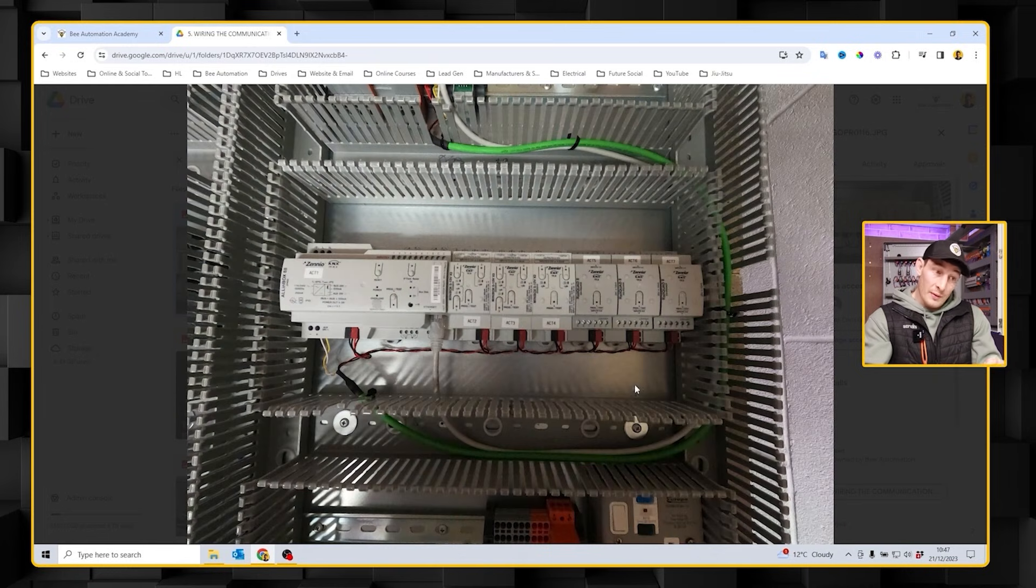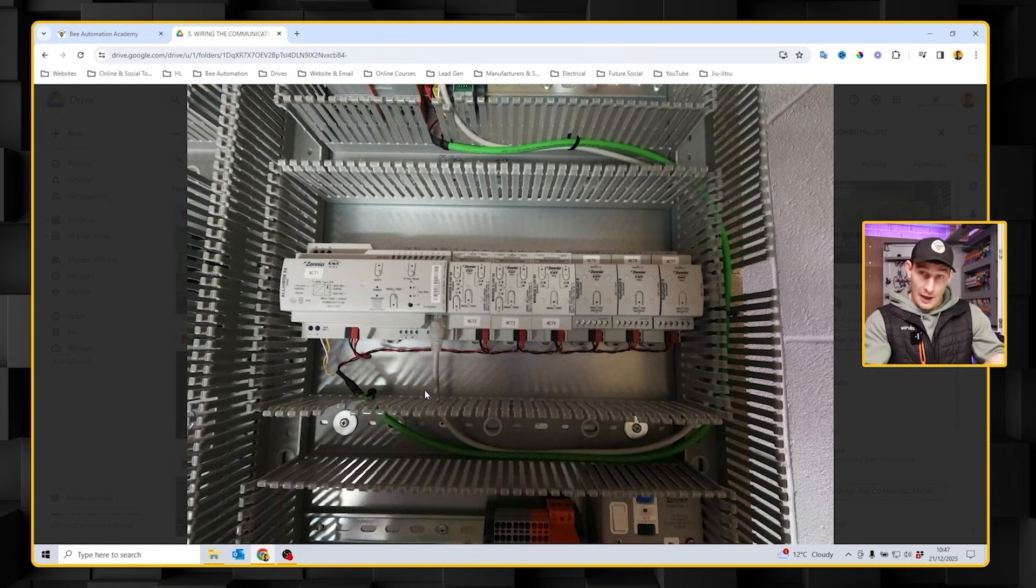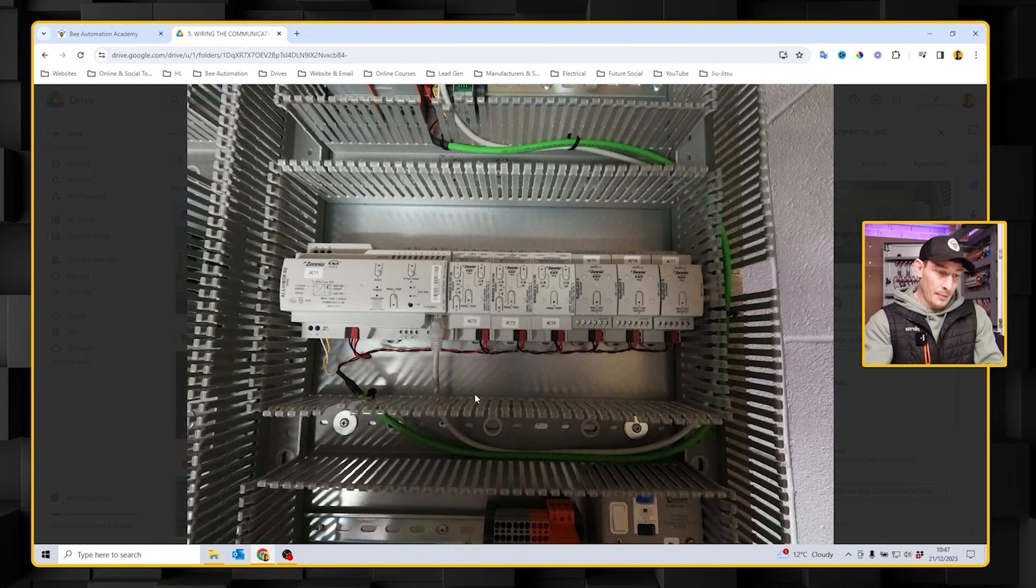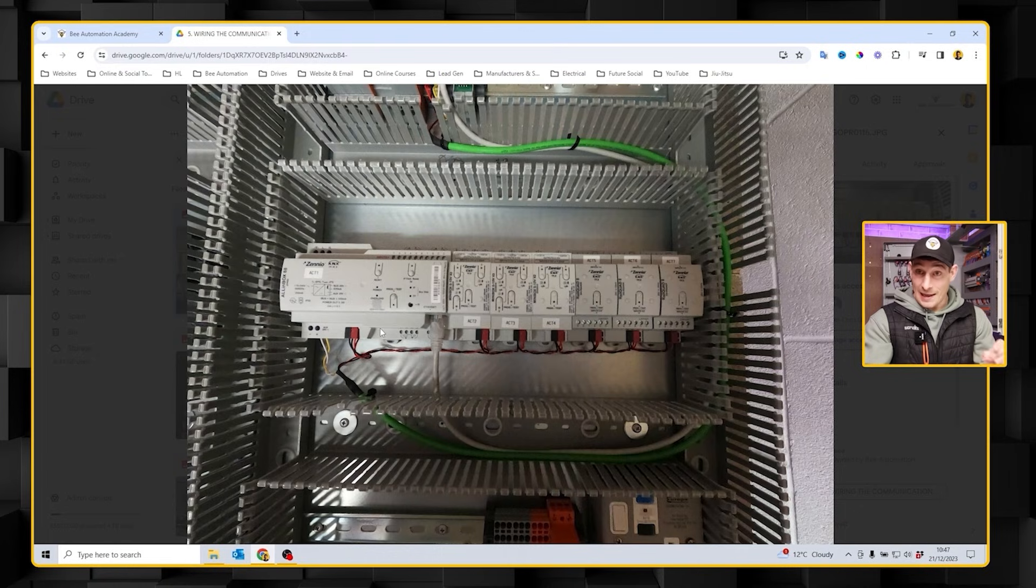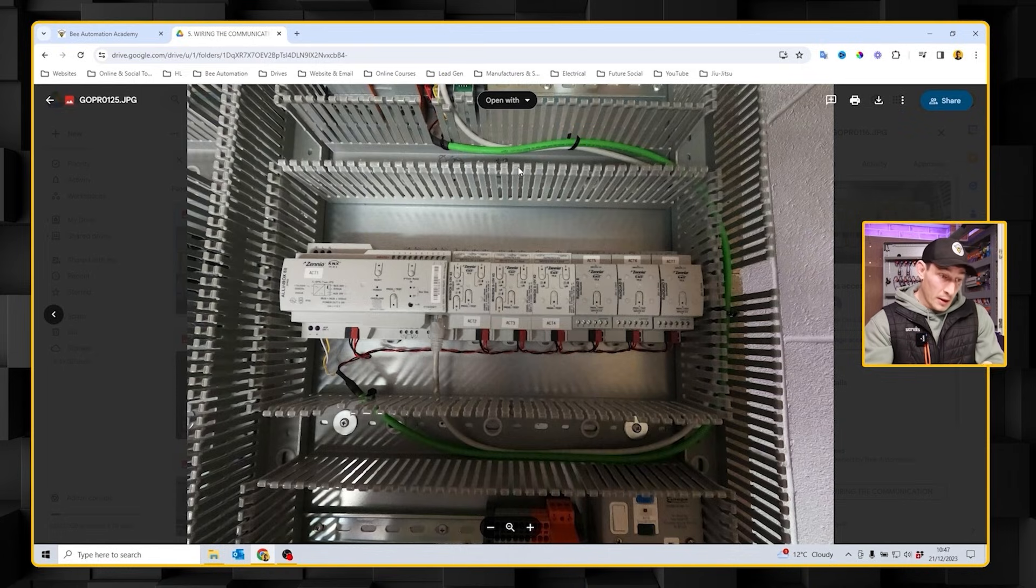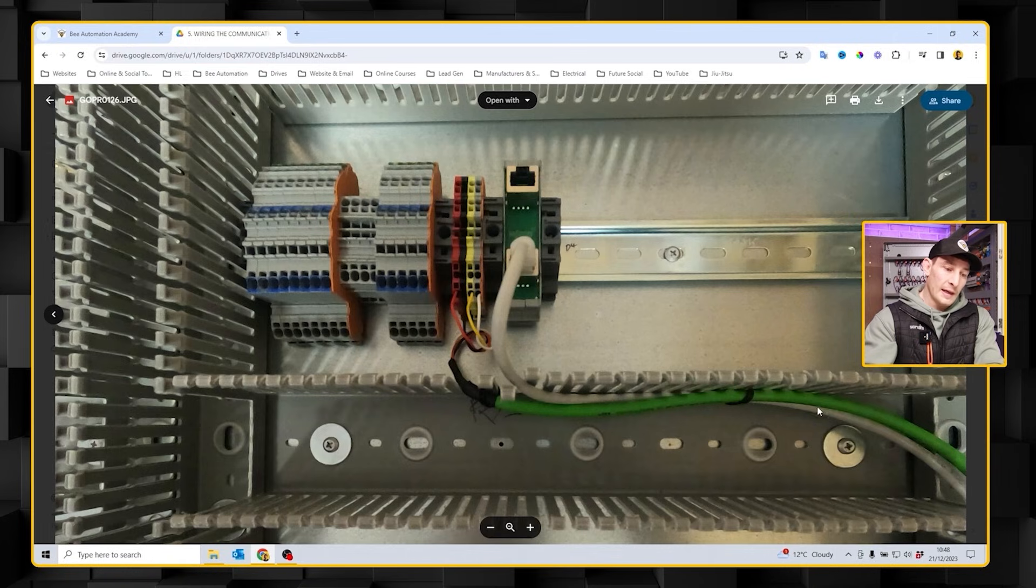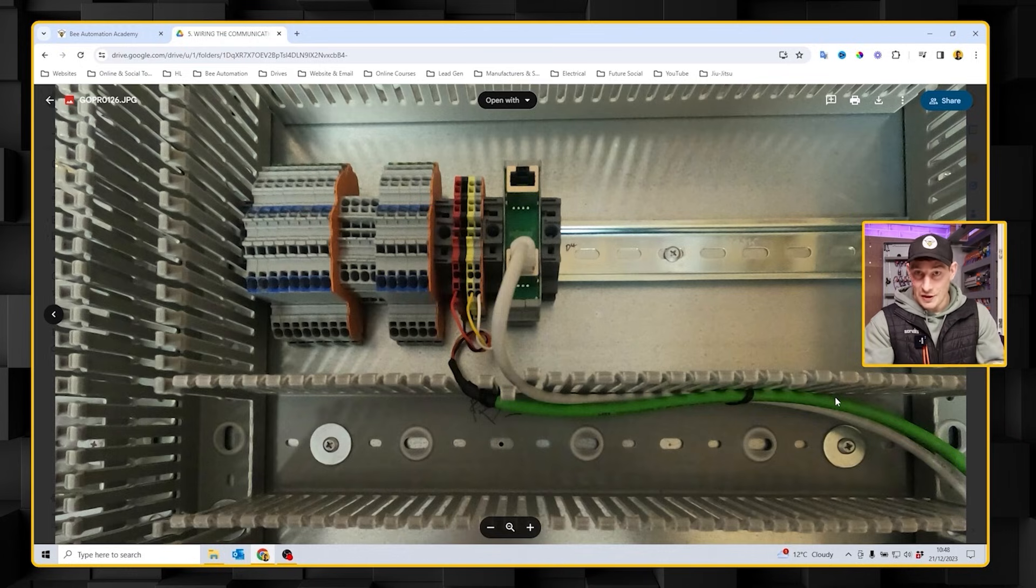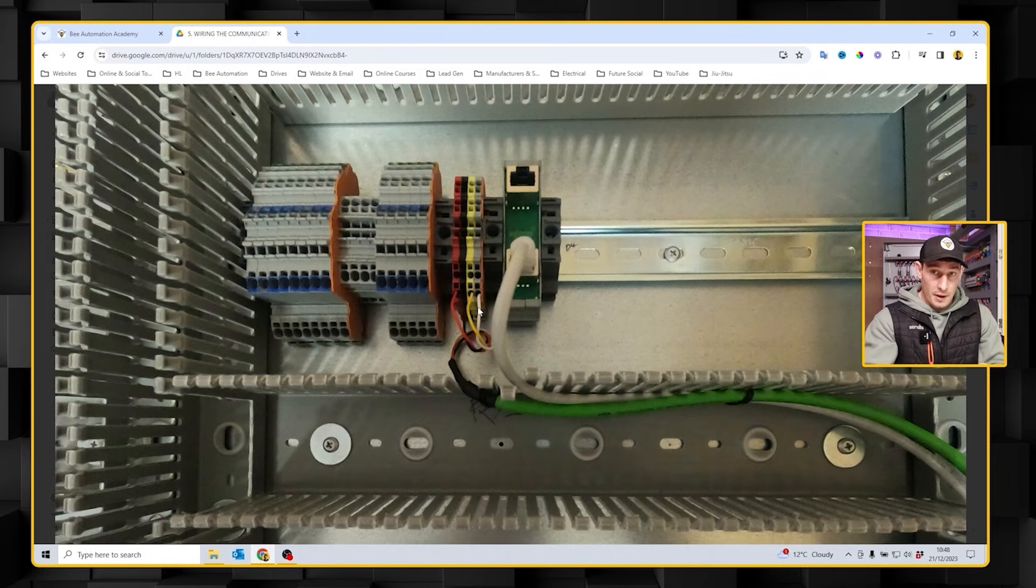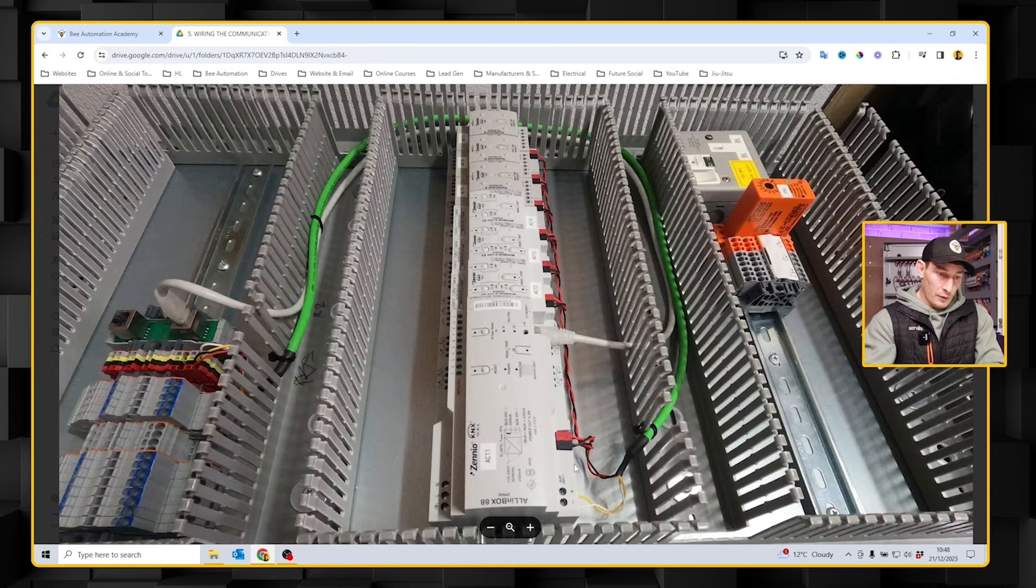So like what we did with the Ethernet cable, you've got the IP connection to the main controller here, but then going out of the panel or meeting another incoming data cable coming into the panel, we're doing the same thing now with the KNX cable. You'll see this green cable is taking that KNX bus up to the top terminals to then allow any KNX devices out in the field to also be on that KNX communication bus. We're keeping it in its full installation here because it's going to be running next to other cables which could potentially induce noise.